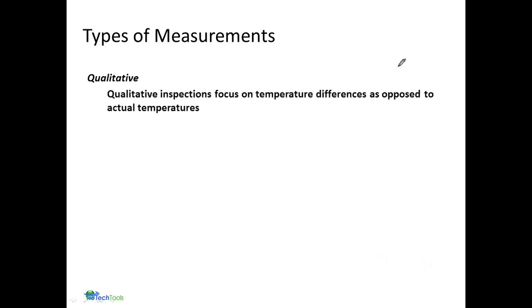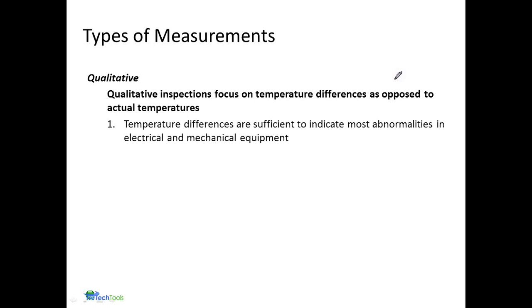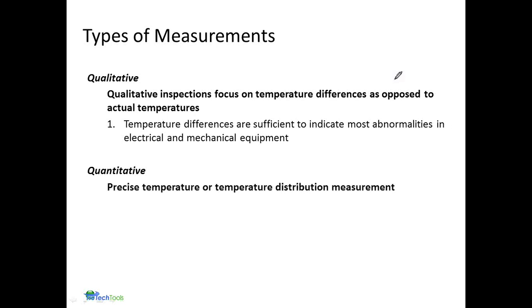As for types of measurements, most imagery in the home environment is qualitative. We're dealing with differences in what's going on in the thermal image, not absolute temperatures. We're concerned about areas where insulation is missing or installed improperly, or areas that are wet, not the absolute temperature values. This is a focus of the Level 1 thermography class. When we get to quantitative measurement, we're dealing with specific temperatures, trying to understand exactly what's going on, but the majority of imagery is qualitative - we're just looking for abnormalities in equipment or structures.